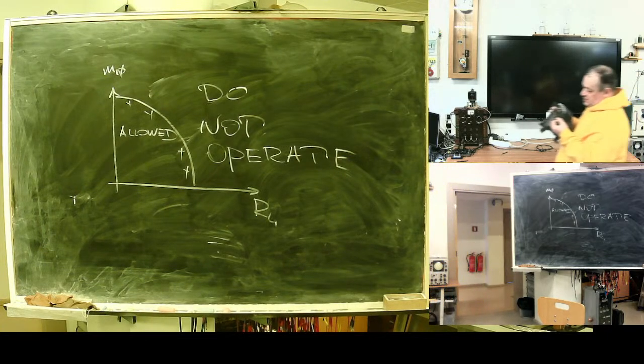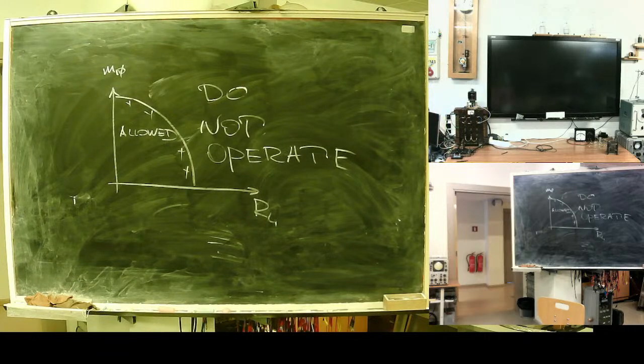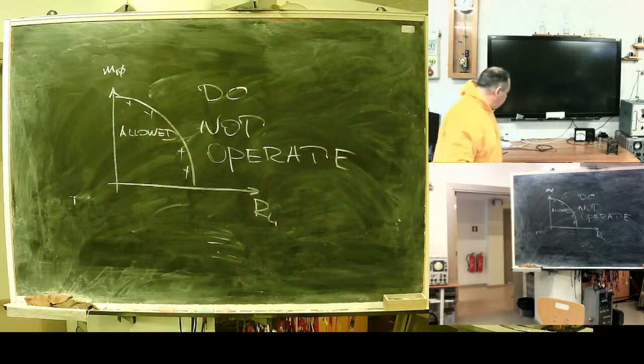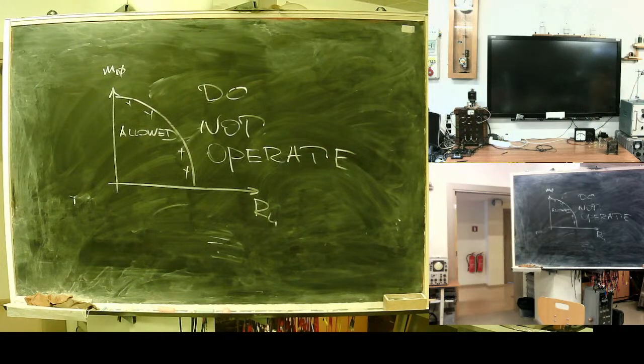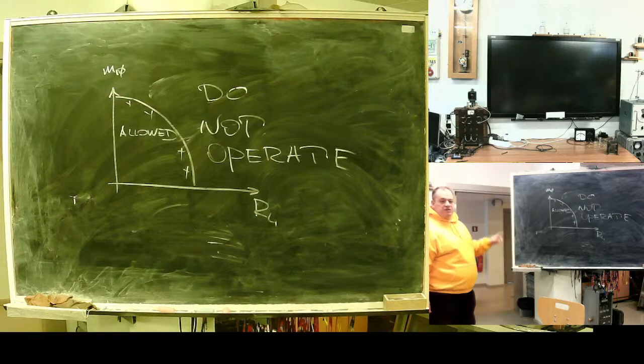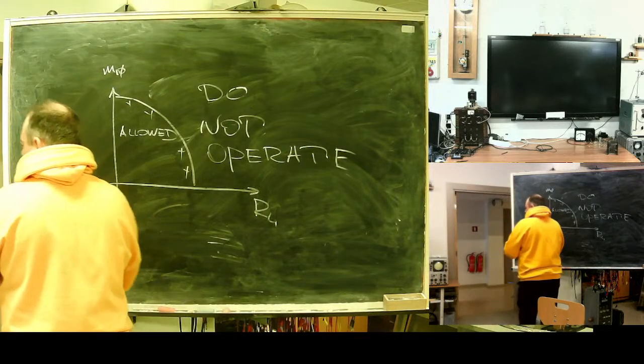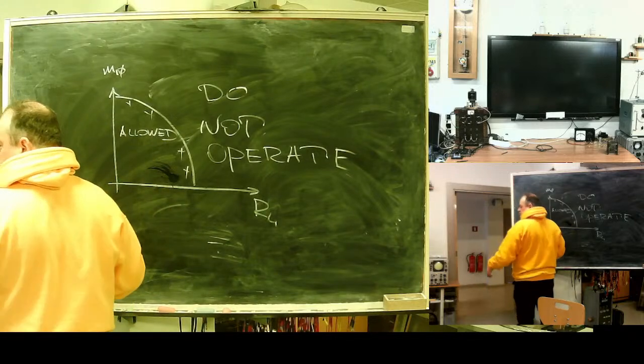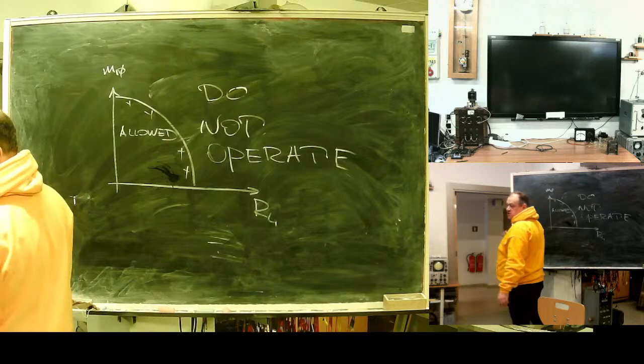Go back. These are the children. One transformer, two transformers, somewhere there should be transformer number 3. Now, the next problem. We spoke about how many transformers? One current transformer. 1000 amps primary, secondary 5 amps, 10 kilovolts insulation, everything fine.